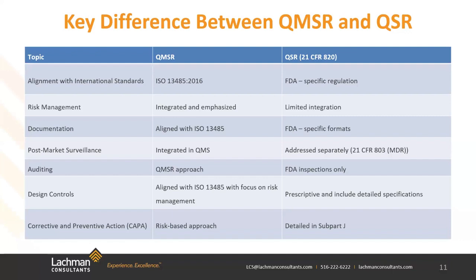The quality management system regulation emphasizes a risk-based approach throughout the quality management system, from design to your post-market activities, as well as fully integrates the risk management principles, aligning to, as David mentioned earlier, ISO 14971, risk management for medical devices. This change ensures an effective risk management system provides the framework for sound decision-making within your quality management system to provide assurance that the devices will be safe and effective, whereas your QSR includes risk-related provisions, but does not explicitly require a comprehensive risk-based approach across all quality management systems.